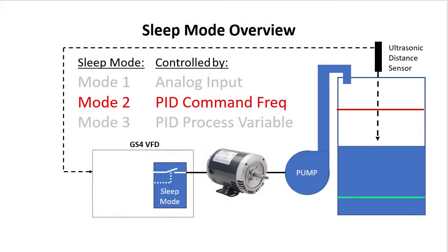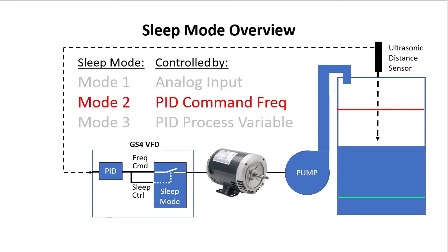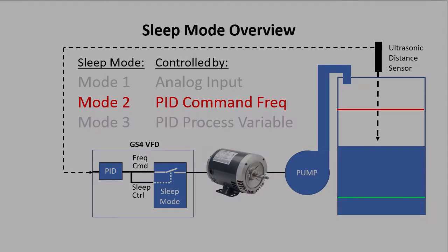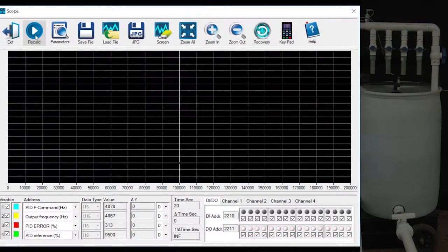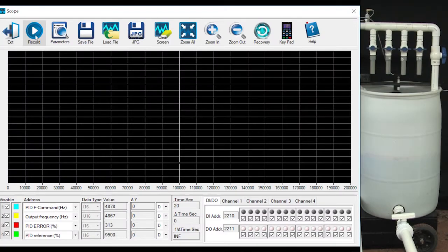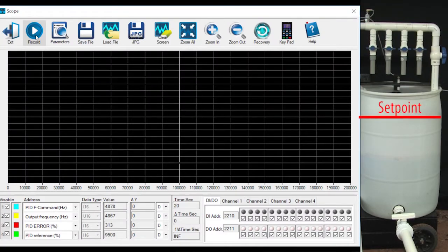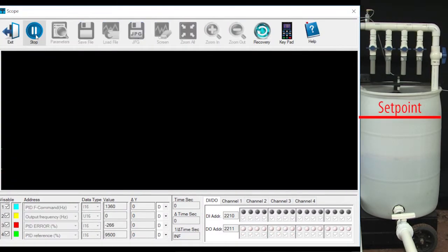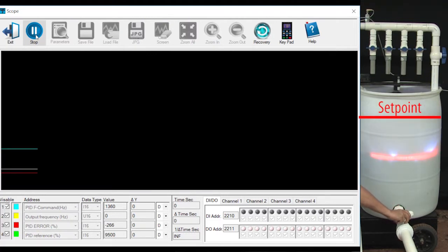Sleep Mode 2 uses the PID generated frequency command to decide when to automatically turn the motor on and off. This is especially important in applications like PID driven tank filling. I have PID set up to fill this tank to this level. Let's turn the water level LEDs on to make that easier to see and open the valve a little to create some demand.